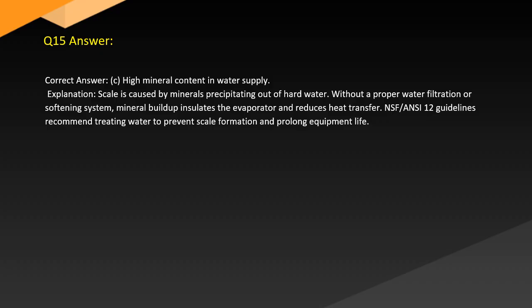Answer. Correct answer: C. High mineral content in water supply. Explanation: scale is caused by minerals precipitating out of hard water without a proper water filtration or softening system. Mineral buildup insulates the evaporator and reduces heat transfer. NSF/ANSI 12 guidelines recommend treating water to prevent scale formation and prolong equipment life.